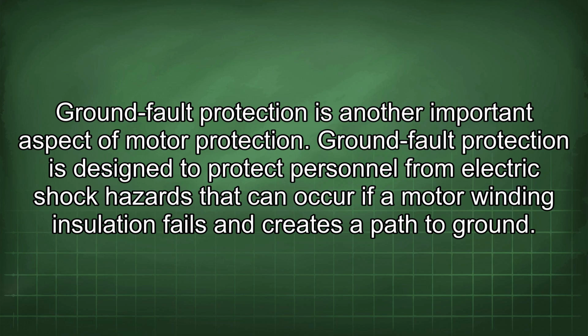Ground fault protection is another important aspect of motor protection. Ground fault protection is designed to protect personnel from electric shock hazards that can occur if a motor winding insulation fails and creates a path to ground.